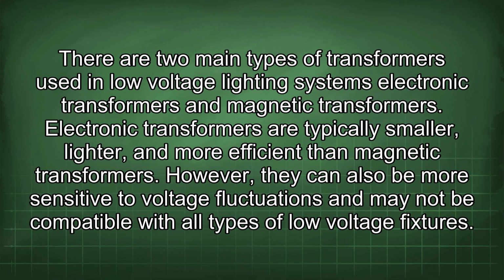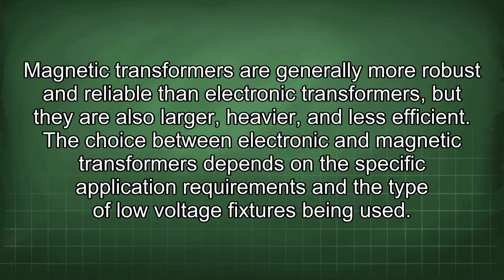There are two main types of transformers used in low-voltage lighting systems: electronic transformers and magnetic transformers. Electronic transformers are typically smaller, lighter, and more efficient than magnetic transformers. However, they can also be more sensitive to voltage fluctuations and may not be compatible with all types of low-voltage fixtures. Magnetic transformers are generally more robust and reliable than electronic transformers, but they are also larger, heavier, and less efficient.